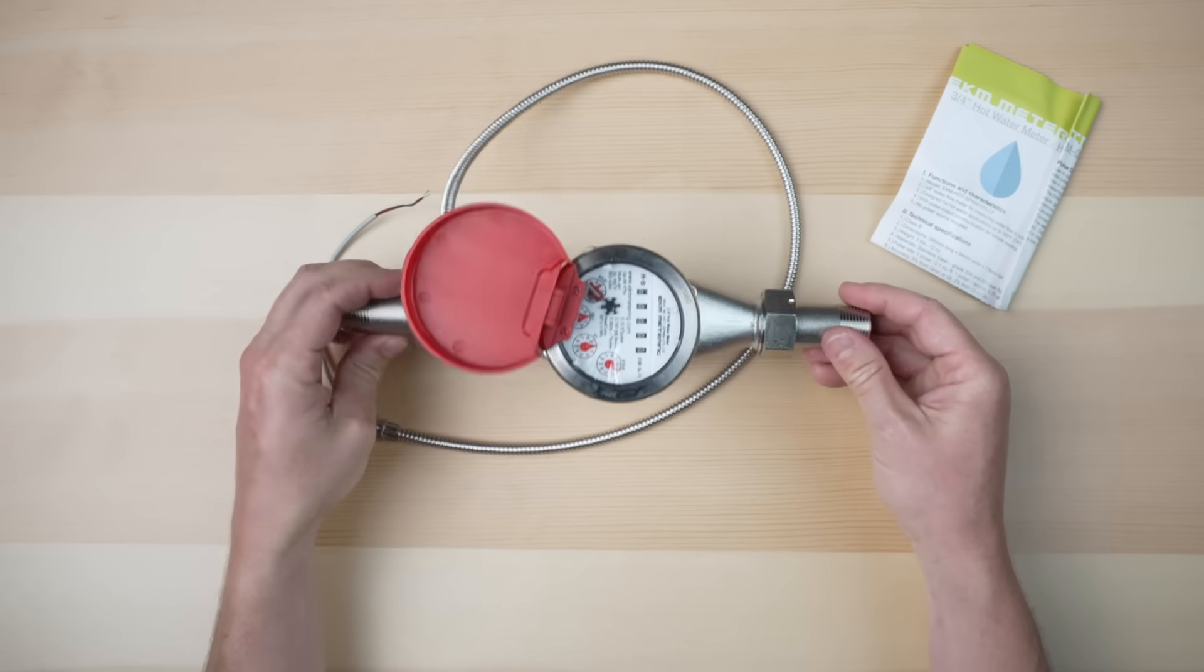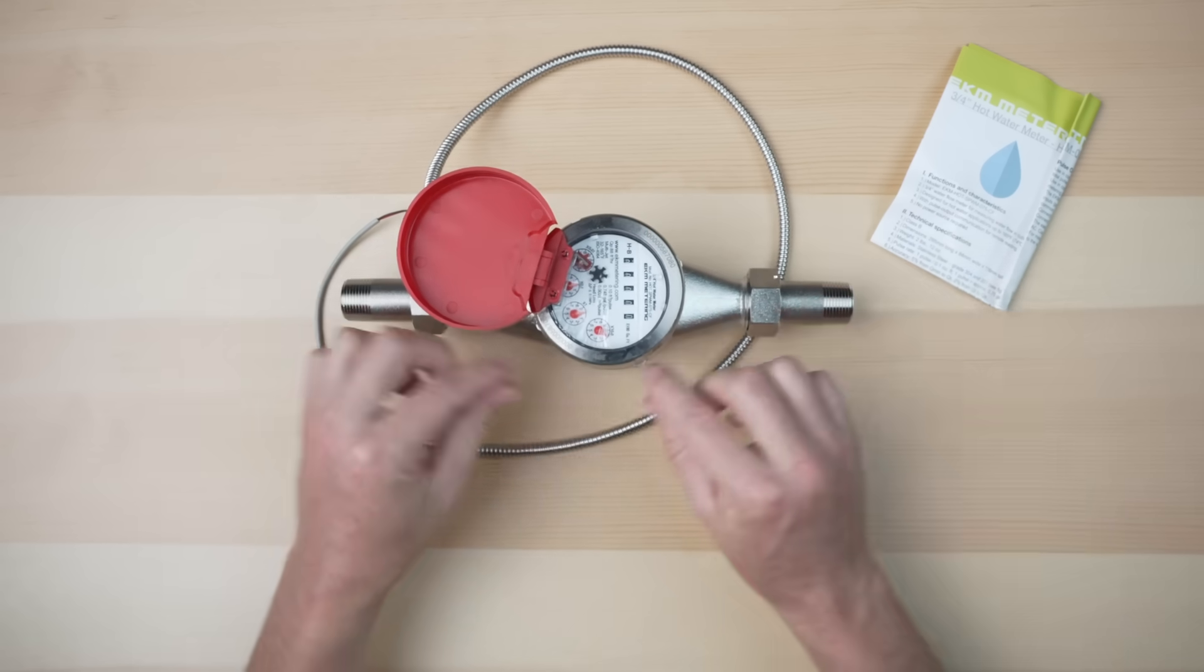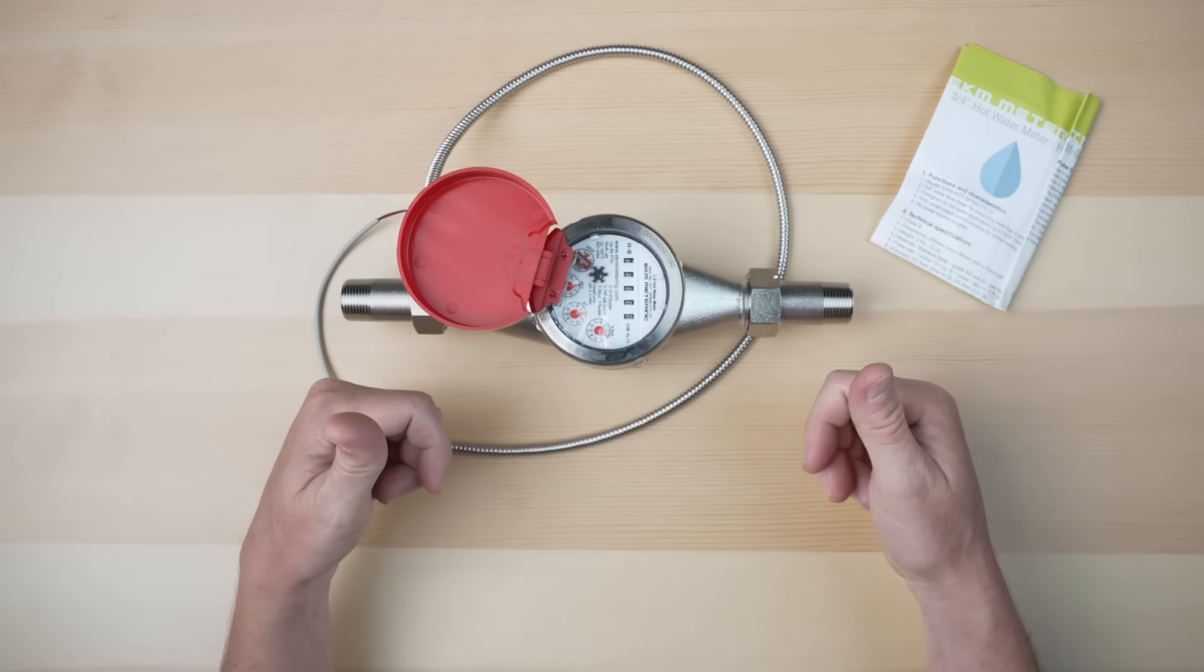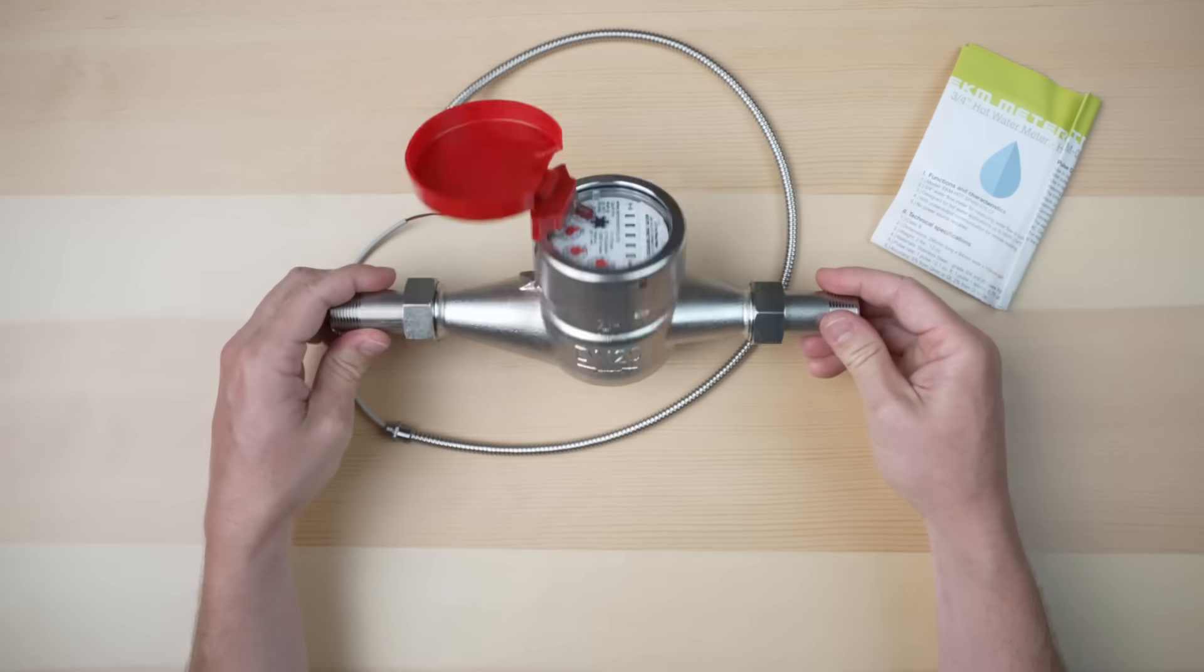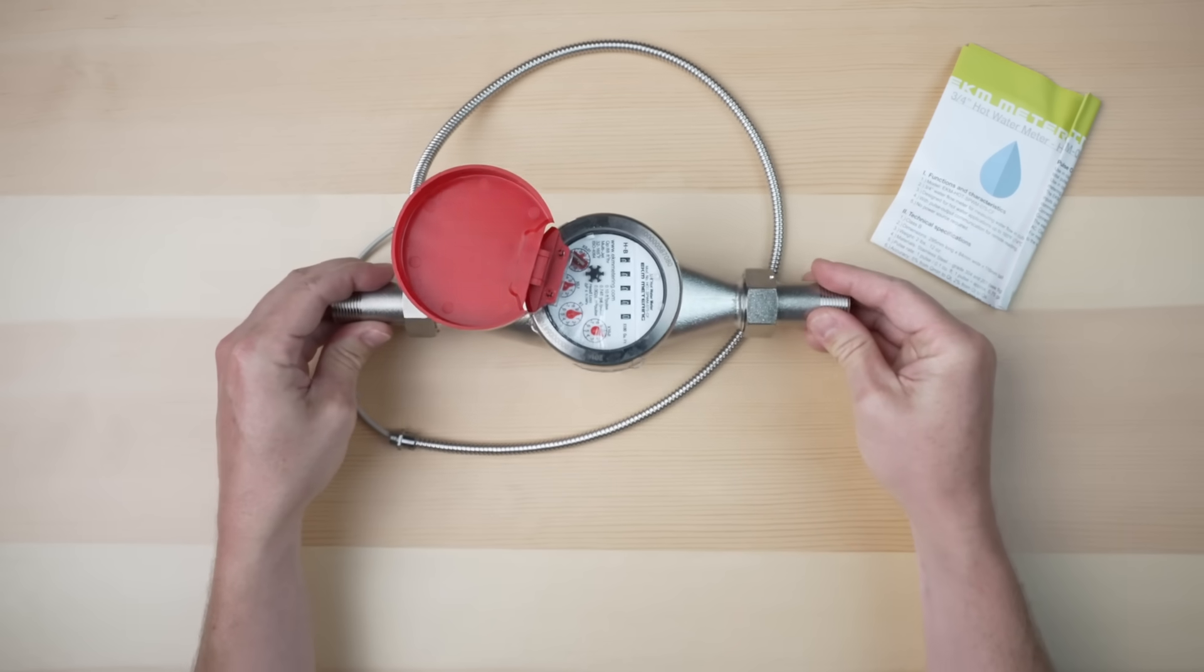This is a horizontal water meter, so it must be installed horizontally with the dials facing upwards. Installed at any other orientation and it will not meter accurately.